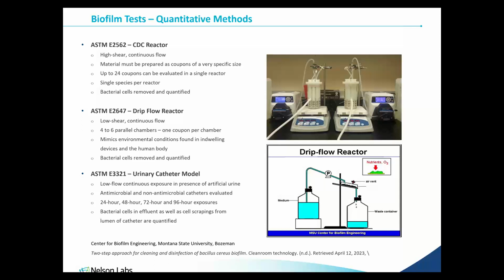The coupons are tailor-made from the desired test material or materials and then examined simultaneously in a single assay. Individual coupons can be removed or exchanged during the experiment, allowing time course studies. The rotation of the baffled stir bar within each reactor leads the coupons to undergo a consistent high shear. Nutrients are continuously pumped into and out of the reactor at the same rate. These stress conditions promote biofilm formation on the test surfaces.